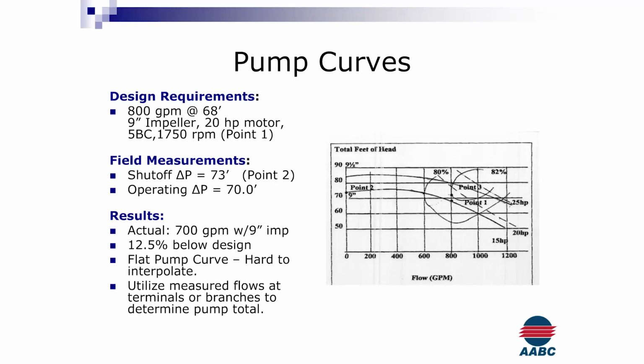Pump curves. A lot of the times when we get out to a pump, it's way different than air side. We can drill a hole or open up an access door on the duct side, send a camera down the duct, and see what's going on for obstructions or anything. On the pump side, it's way harder to troubleshoot. We've got a couple of gauges, maybe a triple duty valve, and then some outlets that we can go down, and maybe some zone valves if we're lucky, so that we can kind of back into some of the things we're seeing in a pump.